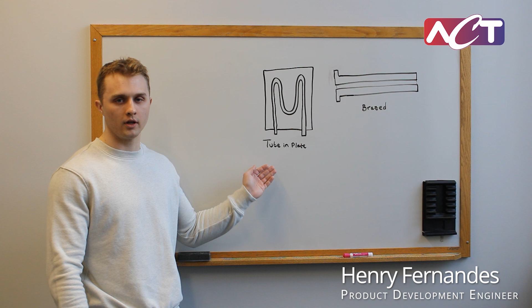Typically for a cold plate, you have either a tube-in plate or a brazed design. For a tube-in plate, you have some type of copper tubing, typically epoxied or soldered into an aluminum tray. For brazed designs, aluminum is typically used, with two halves brazed together. Sometimes this can be a lid, where it forms two halves of a cold plate, allowing complex flow path geometries to be machined internally before the two pieces are brazed together.